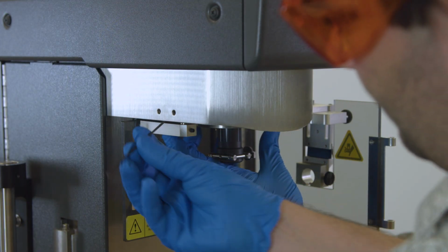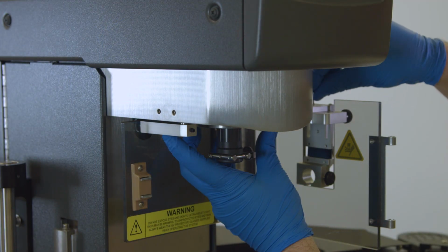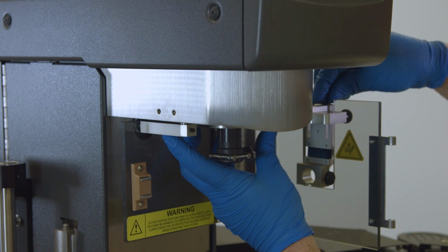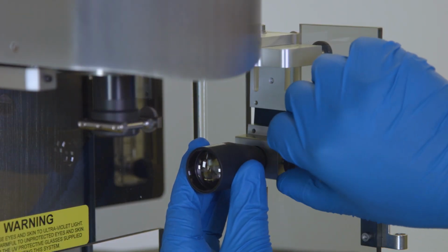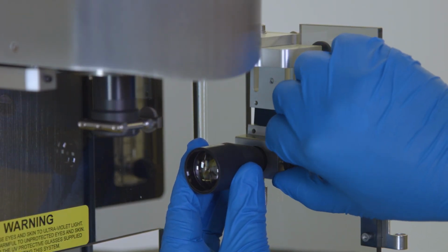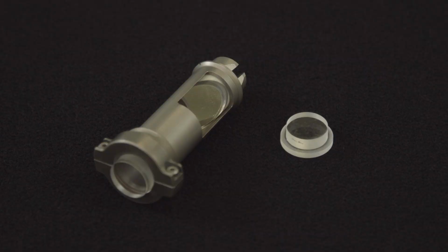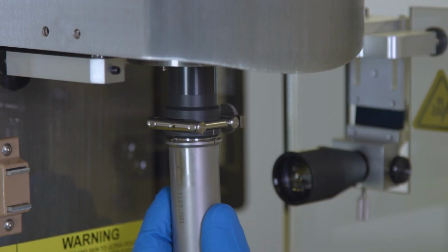Attach the back of the UV light shield to the upper mounts on the ARES-G2 using the 2mm hex keys. Obtain the collimating lens and affix it to the light shield with the black knurled knob. Attach the UV upper geometry with the mirror facing the collimating lens and the scribe mark aligned as shown.